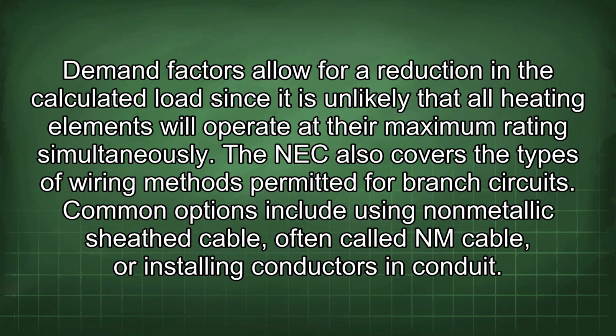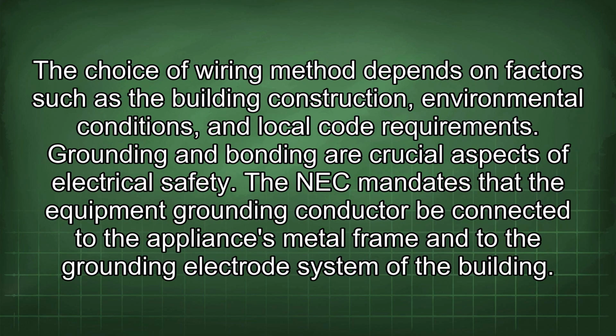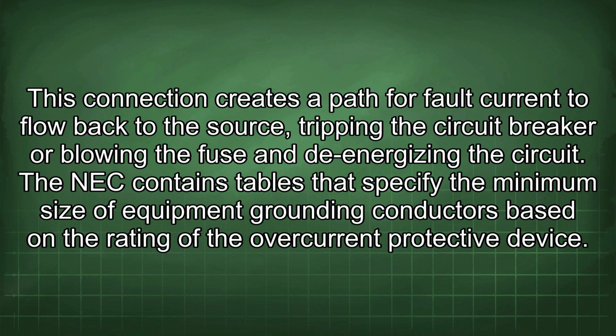The NEC also covers the types of wiring methods permitted for branch circuits. Common options include using non-metallic sheathed cable, often called NM cable, or installing conductors in conduit. The choice of wiring method depends on factors such as the building construction, environmental conditions, and local code requirements. Grounding and bonding are crucial aspects of electrical safety. The NEC mandates that the equipment grounding conductor be connected to the appliance's metal frame and to the grounding electrode system of the building. This connection creates a path for fault current to flow back to the source, tripping the circuit breaker or blowing the fuse and de-energizing the circuit.